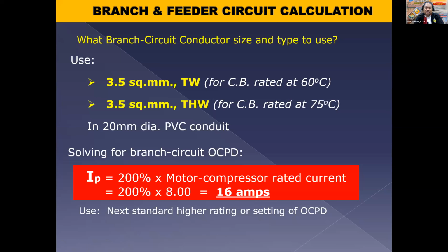Okay, again, let's check. So still within, or perfectly 2.5 times, no? So diyan lang pag-evaluate, na if okay pa ba the next size higher, no? So it's still within 2.5 times dun sa FLC. So protected pa rin yung kuha natin sa short circuit and ground fault. Okay?